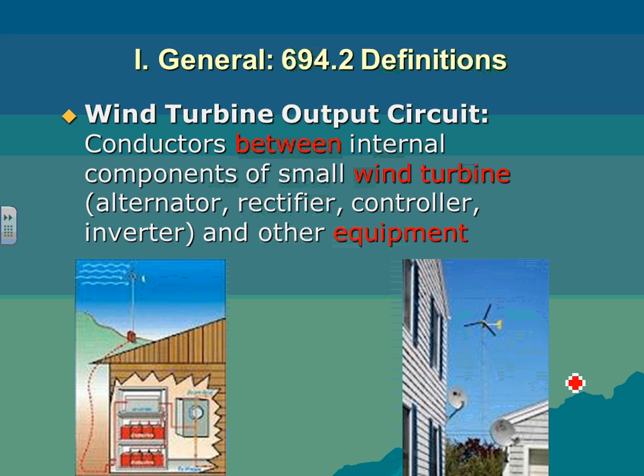There are the bigger turbines, guys, they use doubly fed induction generators. Doubly fed induction generator technology is completely different from this technology. They don't do the inversion. They use induction. Most of the generators that we use are synchronous generators because they're so easy to control the speed. You control the speed of the prime mover, then you can control the frequency. But the wind, you can't control the speed of the wind. You know, it's uncontrollable.